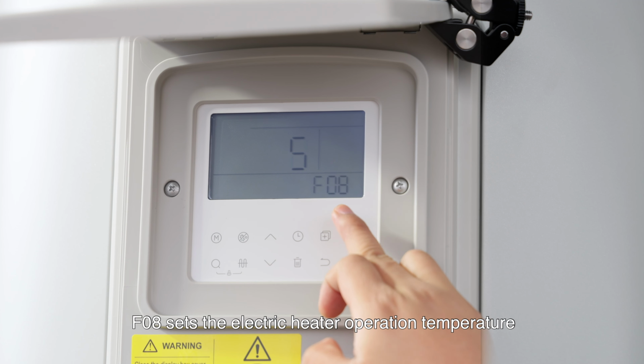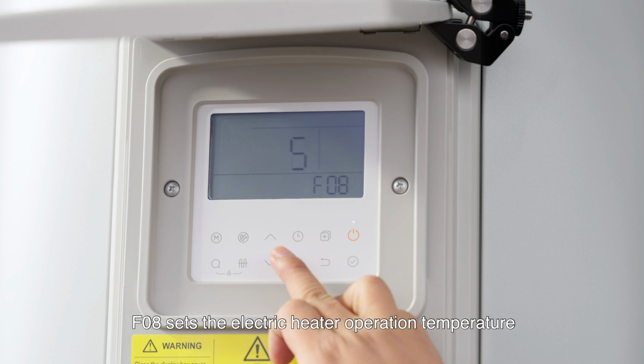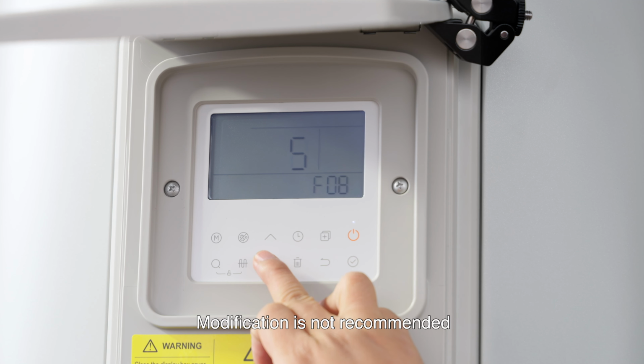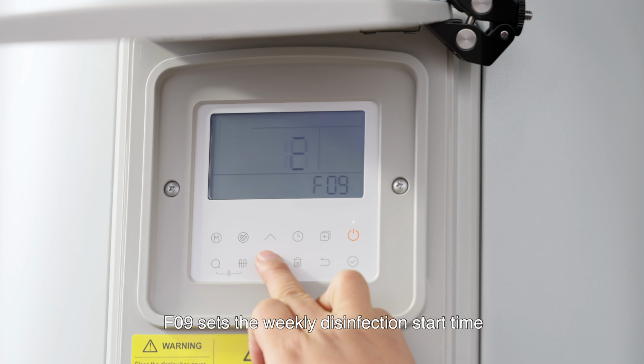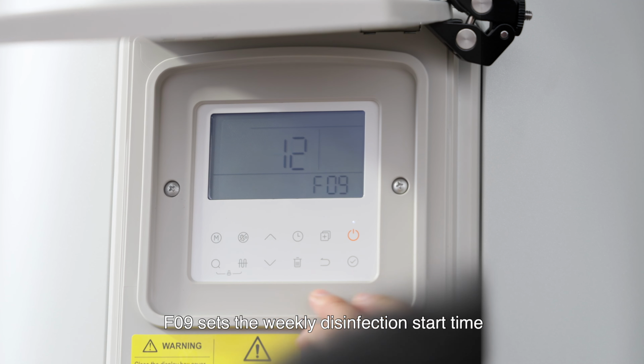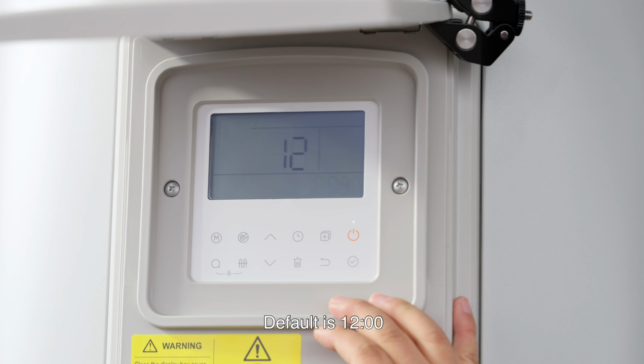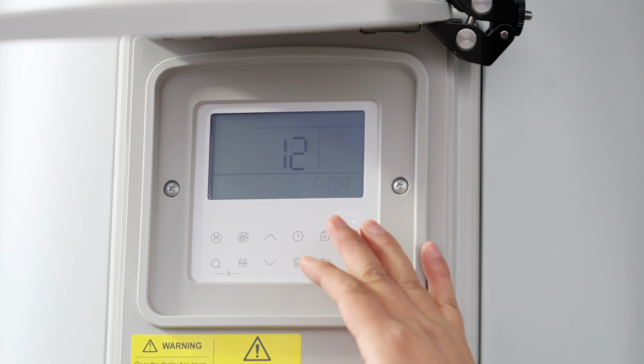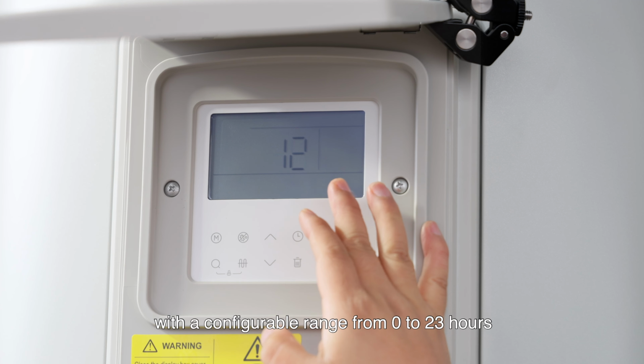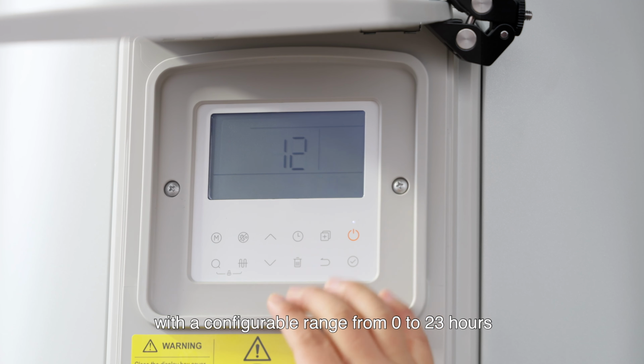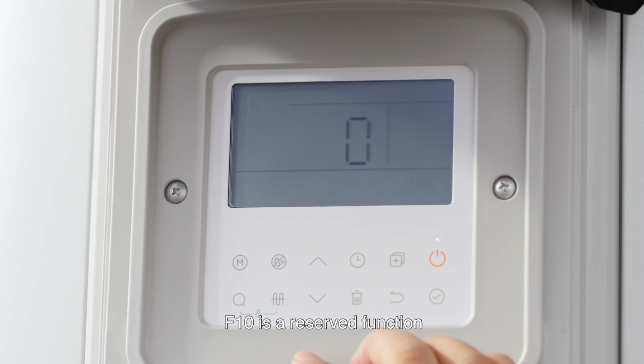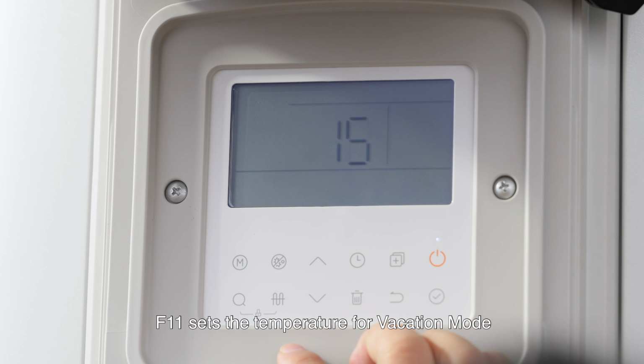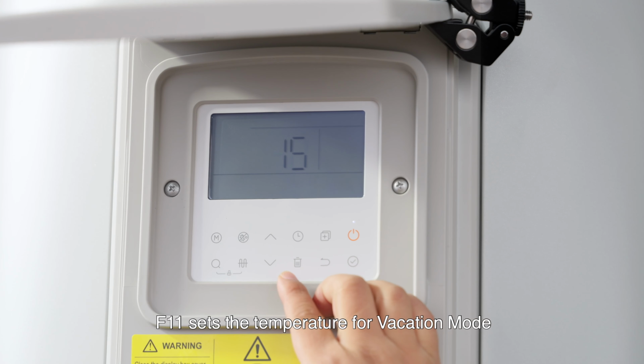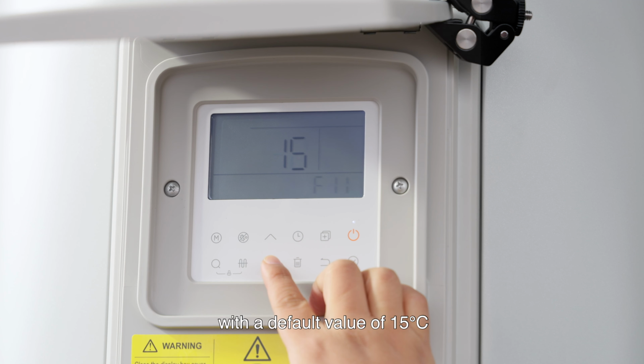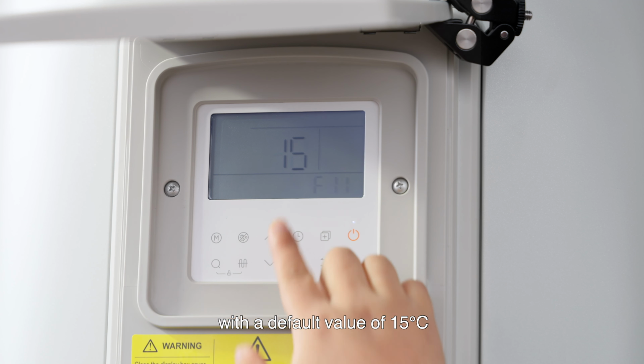F08 sets the electric heater operation temperature. Modification is not recommended. F09 sets the weekly disinfection start time. The default is 12 o'clock, with a configurable range from 0 to 23 hours. F10 is a reserved function. F11 sets the temperature for vacation mode, with a default value of 15 degrees Celsius.